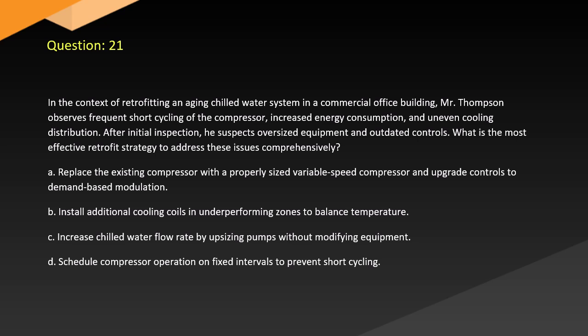Question 21. In the context of retrofitting an aging chilled water system in a commercial office building, Mr. Thompson observes frequent short cycling of the compressor, increased energy consumption, and uneven cooling distribution. After initial inspection, he suspects oversized equipment and outdated controls. What is the most effective retrofit strategy to address these issues comprehensively?